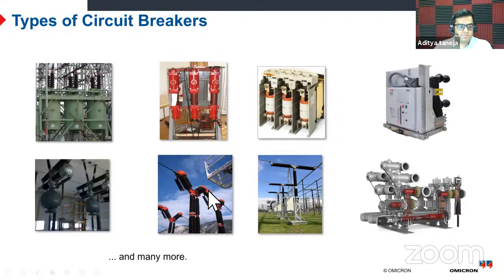And then we have SF6, which is currently the most dominant technology in high voltage. High voltage here means above 66 kV. Below 66 kV and down to 1 kV, vacuum is the most dominant technology. Then there is a new design of the substation itself, where the whole bus is encapsulated in an SF6-filled compartment, called GIS, gas insulated switchgear, which has not only the circuit breakers but also the CTs, VTs, buses, and everything else.